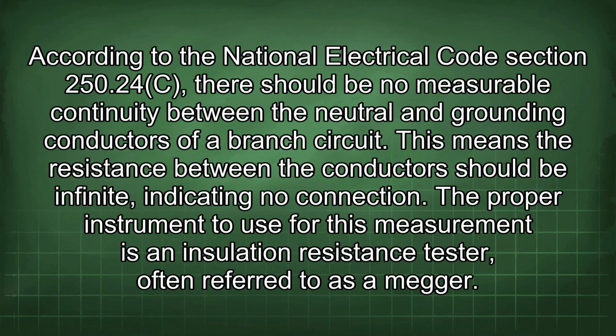According to the National Electrical Code Section 250.24(C), there should be no measurable continuity between the neutral and grounding conductors of a branch circuit. This means the resistance between the conductors should be infinite, indicating no connection. The proper instrument to use for this measurement is an insulation resistance tester, often referred to as a megger.